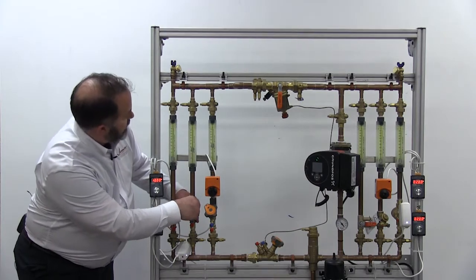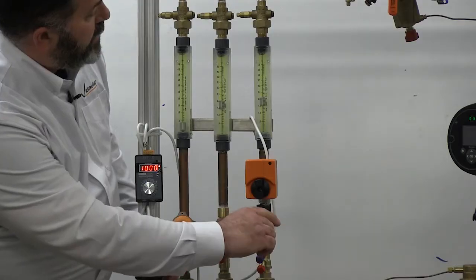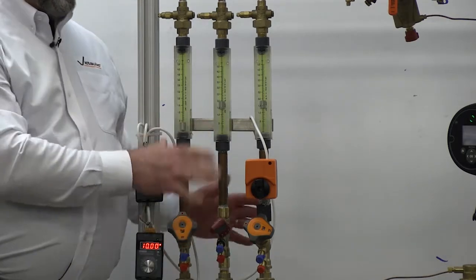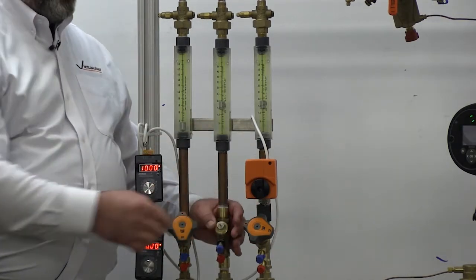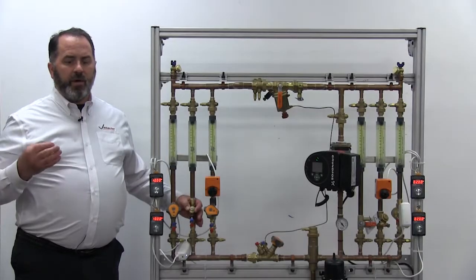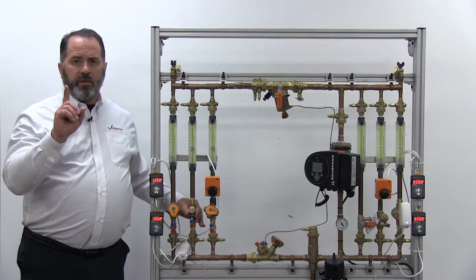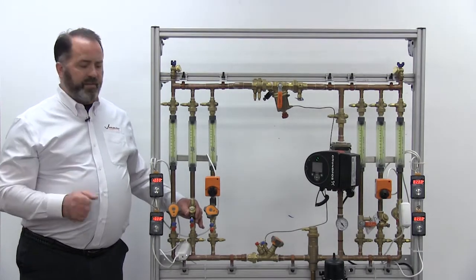Say it's 2 GPM in this case, we'll balance this guy over here to 2 GPM as well. And now I have both systems balanced, but now my control valve also is my balancing valve. I'm giving all of the valve authority, all of the pressure drop for balancing and control to one valve, improving my valve authority.